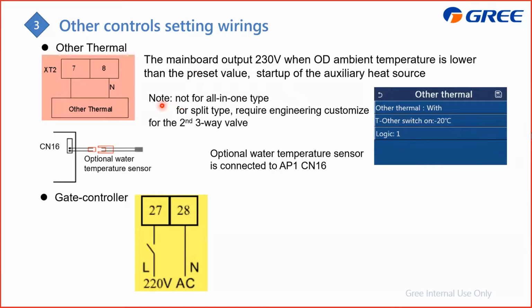And please pay attention that the other thermal is not for all-in-one. For this all-in-one, it is impossible. And for the split type, we require the engineering customized for the second three-way valve. For this one, you need to discuss with our Gree to install another three-way valve. And also for this one, you need to connect with the optional water temperature sensor to detect the water temperature and to set when to turn it on.